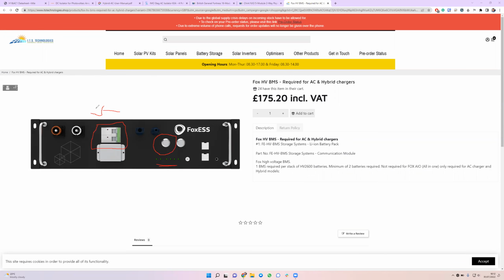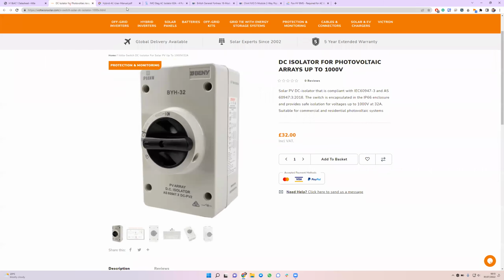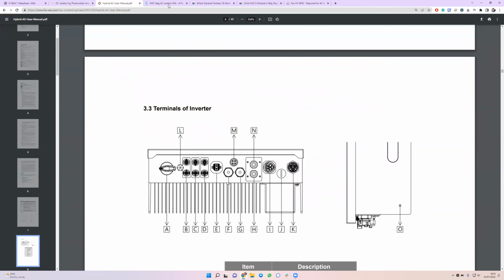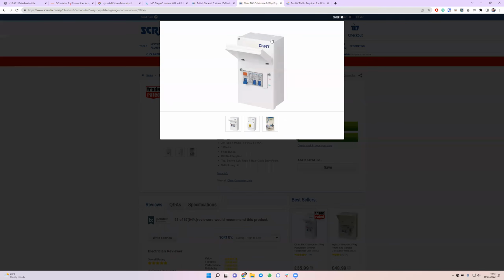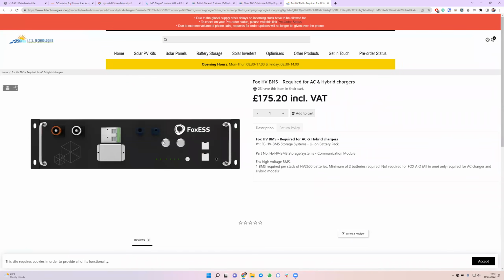I think it goes from right to left for off. It will be obvious which way, because it will be the opposite of what it's on now. And then after a few seconds, you will notice that the screen of the inverter will go blank, and when it's blank, it will also reset some error codes as well. So that's normally the first step of troubleshooting anything: go DC, then AC, one of these options, and then go to the BMS, hit the silver button on the left, and then push the circuit breaker across.